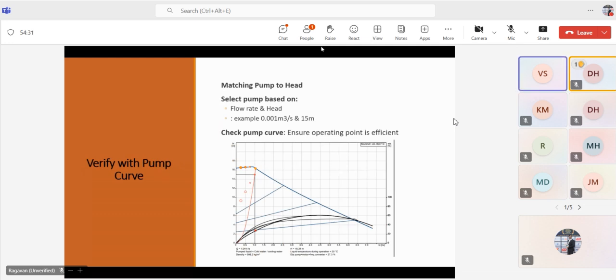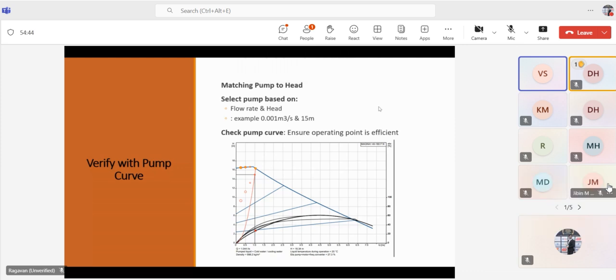Okay. So once you have this value, then you have to select the pump. The major thing is the pump, the chilled water pump. In this slide you can see the pump curve, which is based on the flow rate and the head. So once you have this value, you have to select it here on the pump curve. That is also very important. From here you'll also get the efficiency curve. And move on to the next slide.